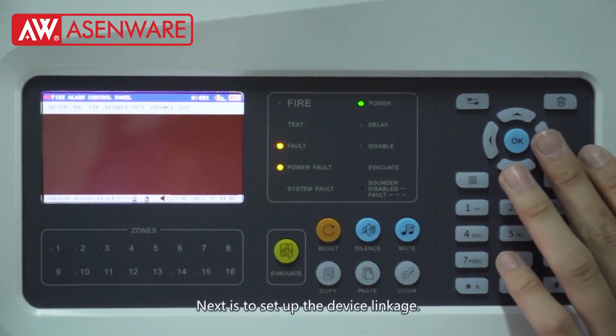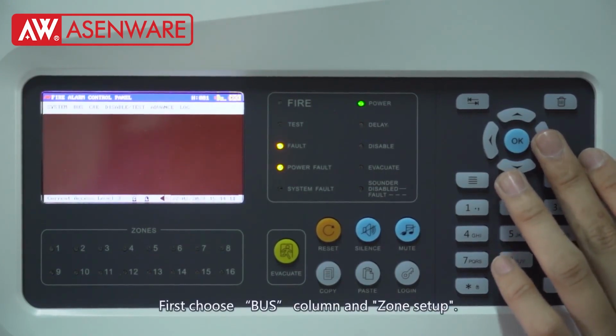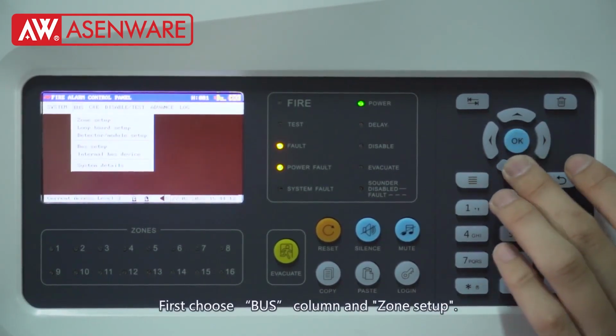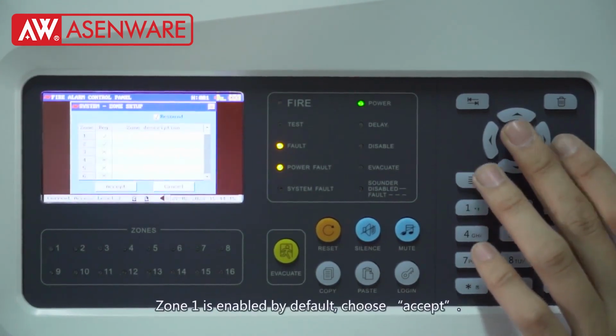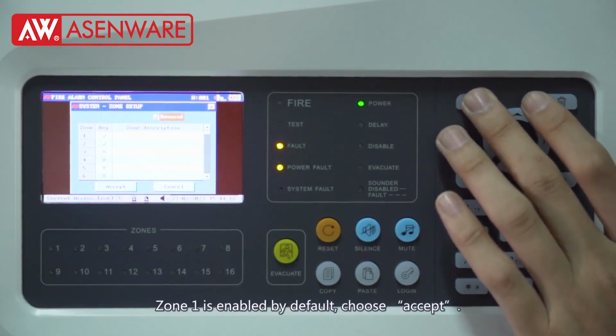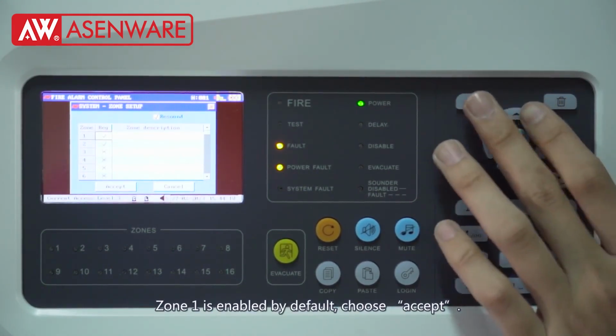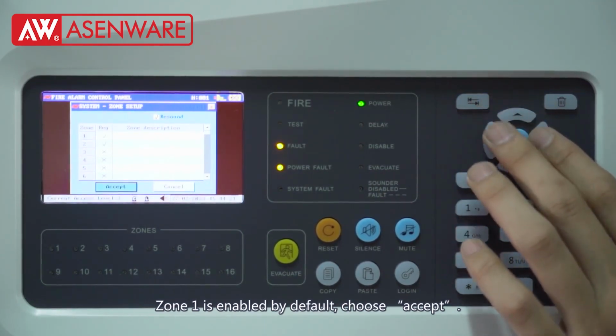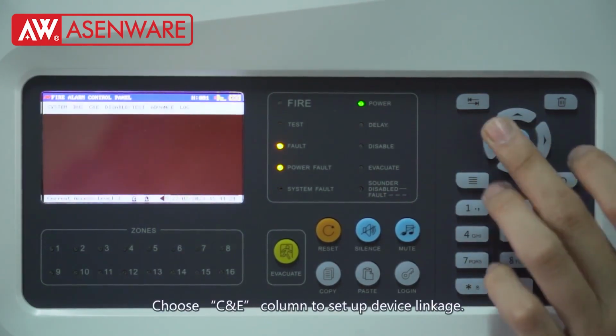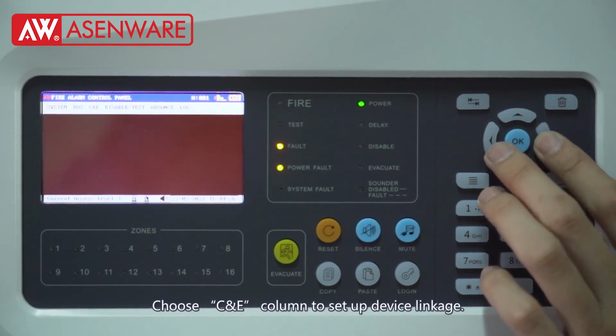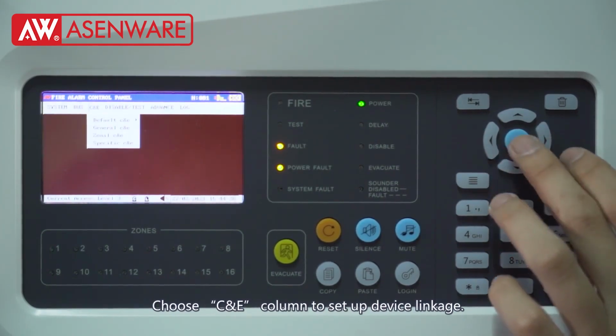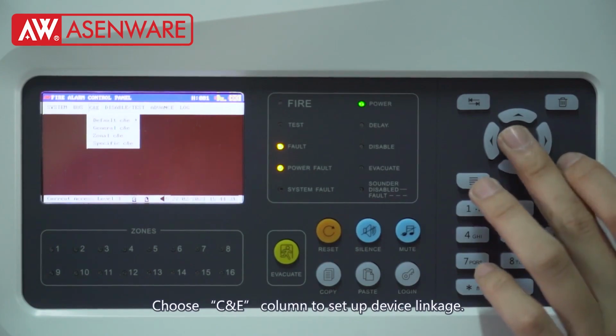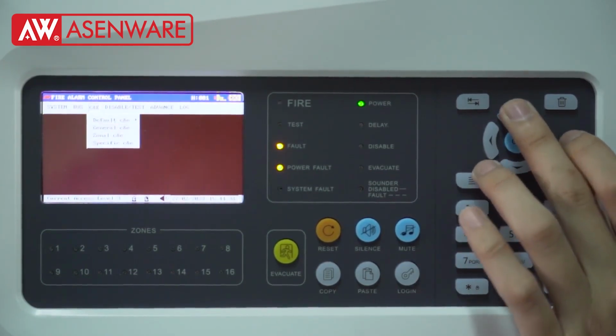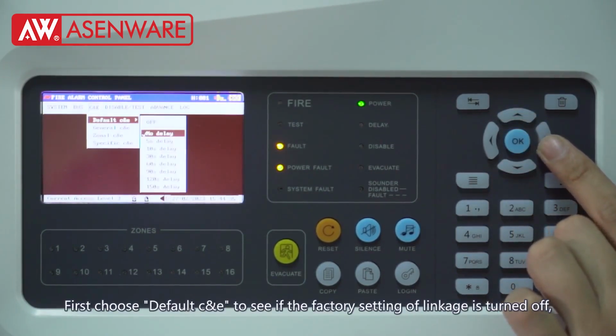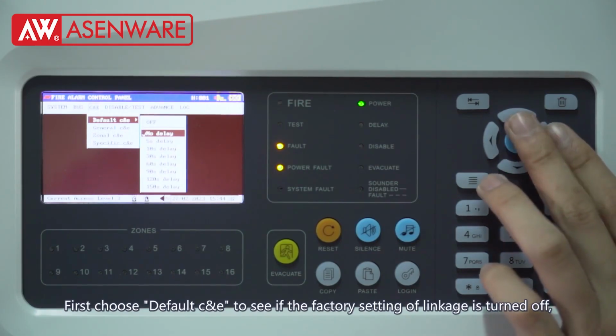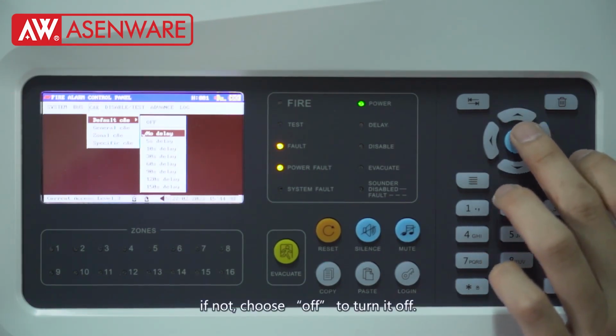Next is to set up the device linkage. First, choose Bus Column and Zone Setup. Zone 1 is enabled by default. Choose Accept. Choose C&E column to set up device linkage. First, choose Default C&E to see if the factory setting of linkage is turned off. If not, choose Off to turn it off.